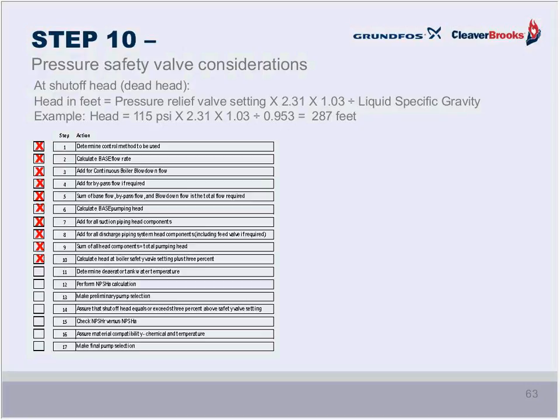All right, then we have to worry about our pressure safety valve settings. The pump has to be capable of achieving a shutoff head or a dead head according to this formula that's defined in the standards. We have to be 3% above that boiler safety valve setting. The spec tells us that that setting was 115 psi, so we do this math, and what we learn is that in addition to achieving that 237 feet at the design flow rate of 23 gallons per minute, the pump also has to be capable of achieving 287 feet at deadhead. A very important calculation that we have to make.